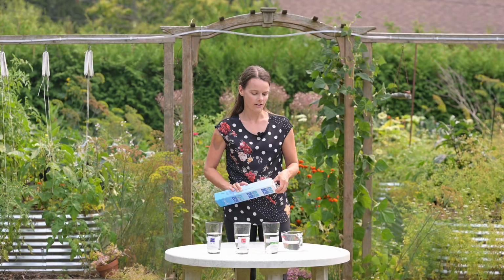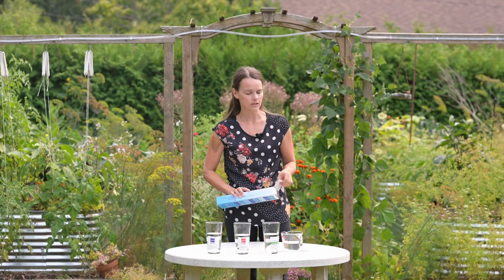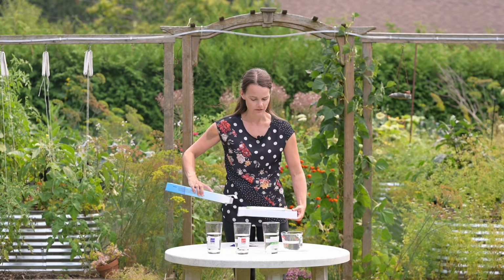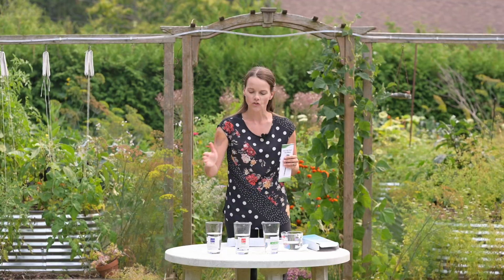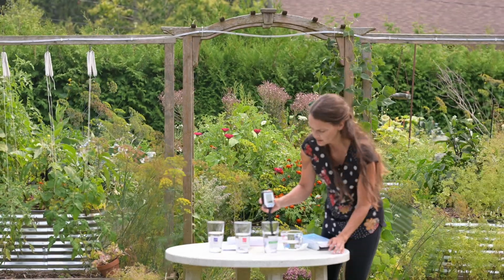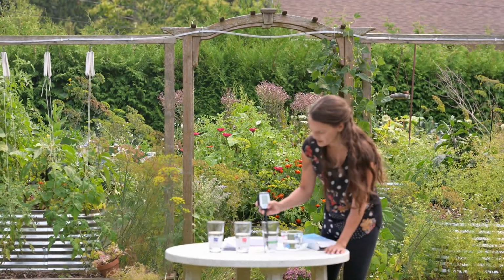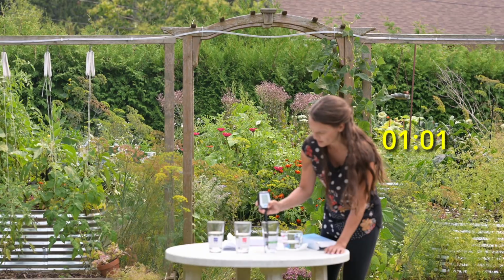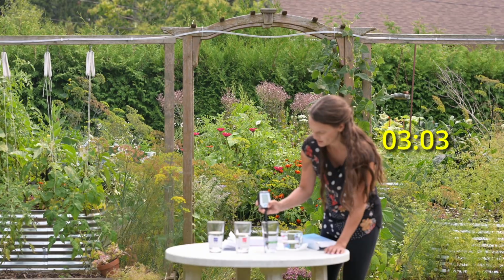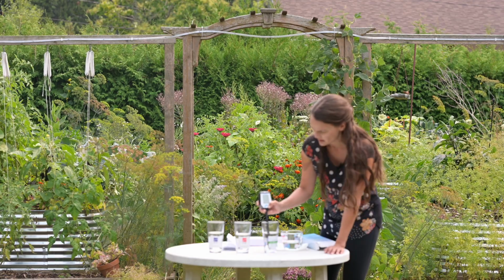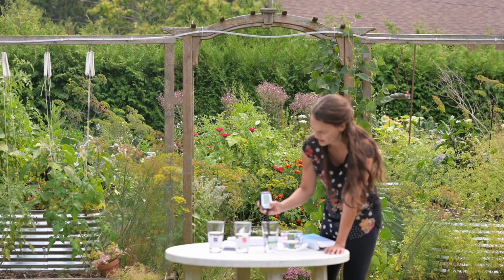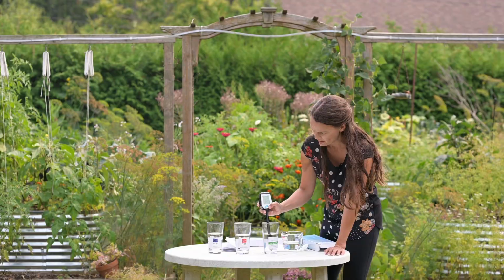Okay, let's try this again. We have gotten a response that I'm supposed to hit the button and hold it for 2 to 3 seconds immediately after it starts blinking. So I've made our solutions, put it in, stir it, I'll press calibrate, and then it starts blinking. So now I go 1, 1000, 2, 1000, 3, 1000, and the 7 is supposed to start blinking. Okay, the pH stopped blinking. Now the 7's supposed to blink.